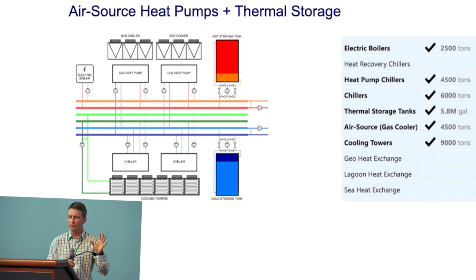We've got a fairly large thermal energy storage resource as part of this plant as well, both on the hot water and the chilled water side. Those are our batteries, right? So we can generate cooling when it's efficient to do so, charge up our chilled water tanks, and discharge them during the 4 to 9 PM period when the grid is constrained and we see our highest demands. Likewise on the heating side.